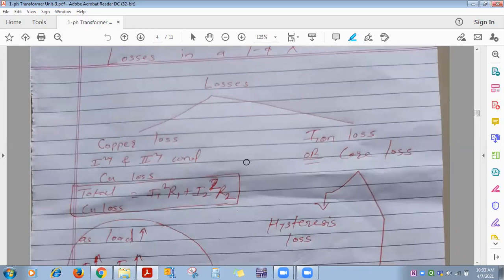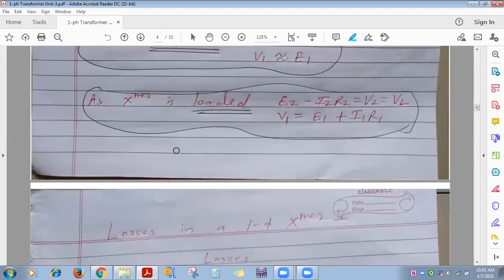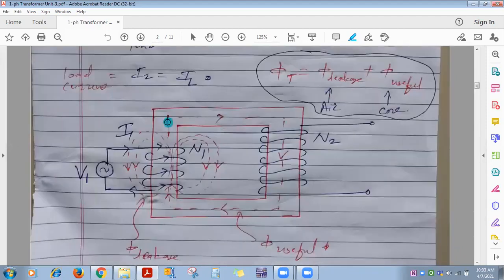Laminated means actually what? Previously also I told you, see, this core here, this one, this is its vertical limb, okay? They manufacture such a plate of these dimensions. Its thickness is 0.3 mm to 0.5 mm. That is one plate. Then a second, horizontal one will also be fitted if it is rectangular, okay? So they manufacture this also of some dimensions. And these plates, horizontal and vertical, their thickness is 0.3 to 0.5 mm silicon steel.